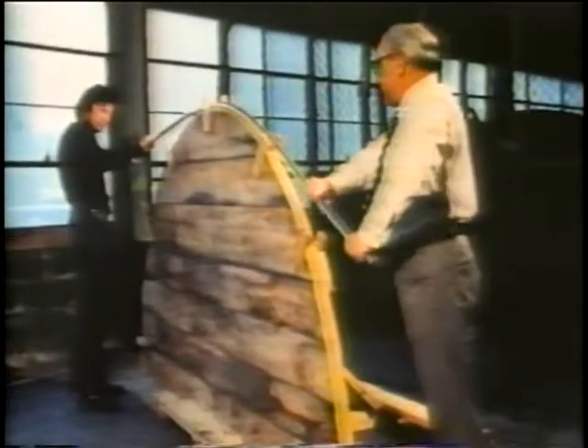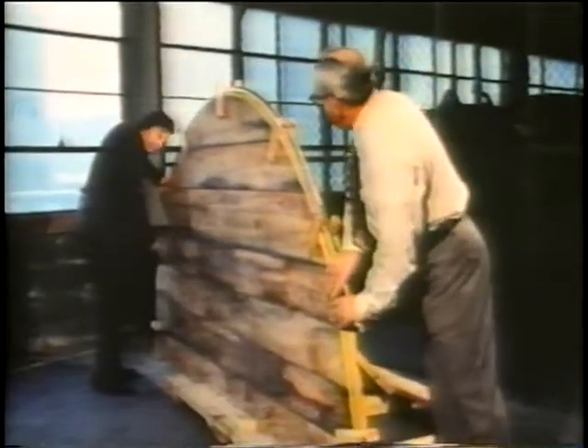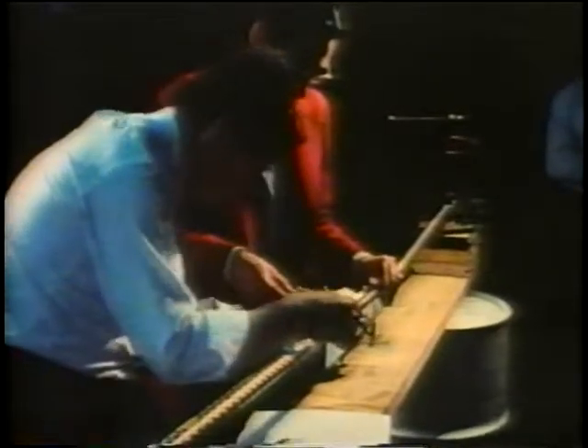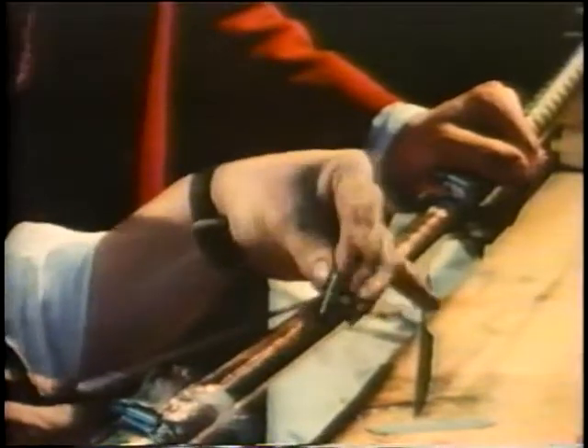The electrical insulation being applied by these machines is another cable component which required extensive development. Cables in lengths of several thousand feet are transported on large reels. A major problem was to develop an insulating material which would not be damaged by the process of reeling and unreeling the cable. After a bend test in the laboratory, the cable is dissected and inspected for damage to the electrical insulation. Later on, these tests were speeded up by the development of a non-destructive X-ray method at Brookhaven.